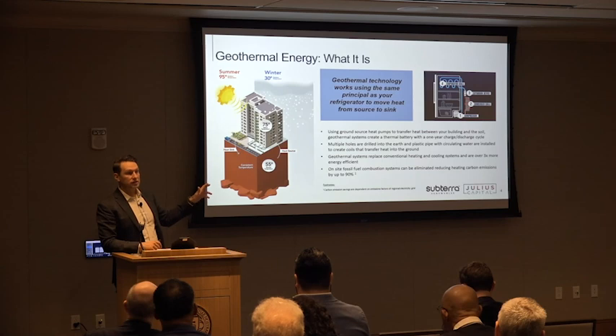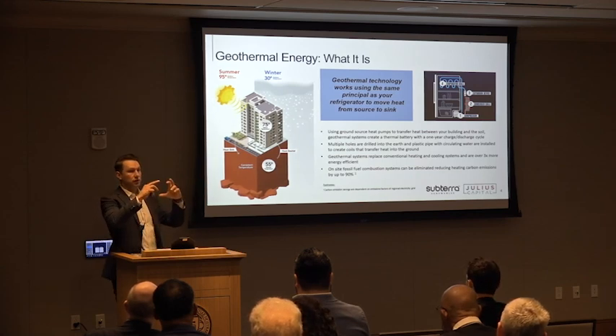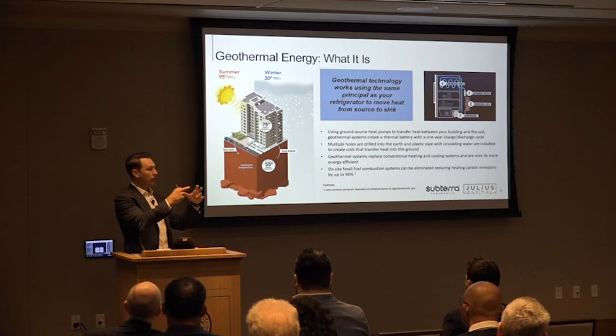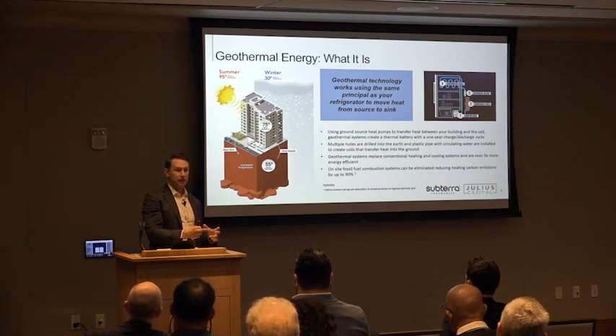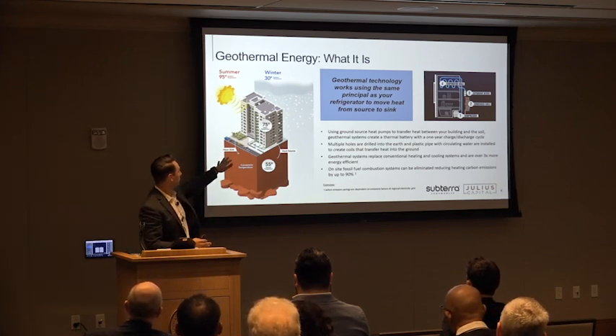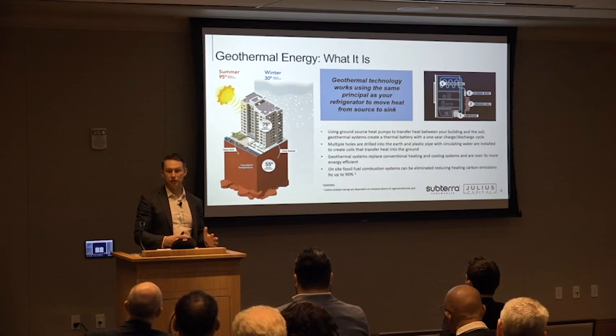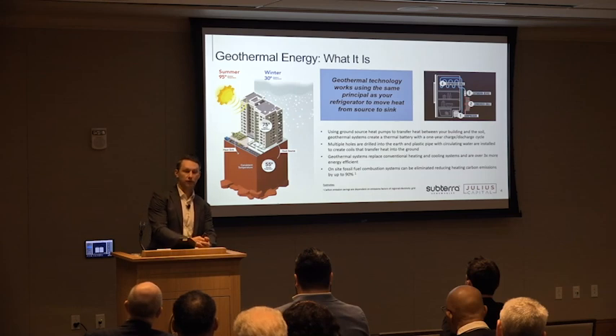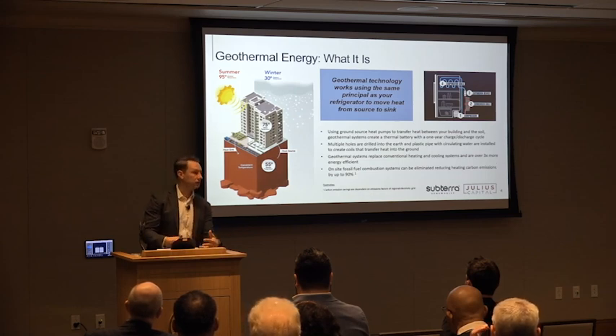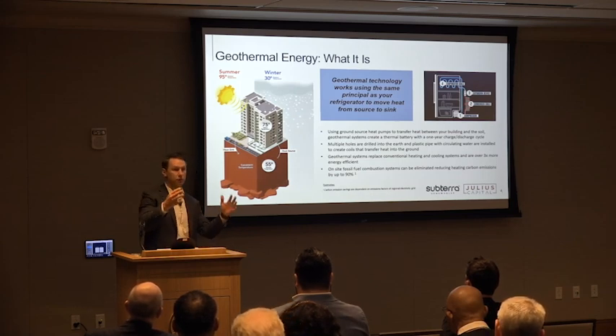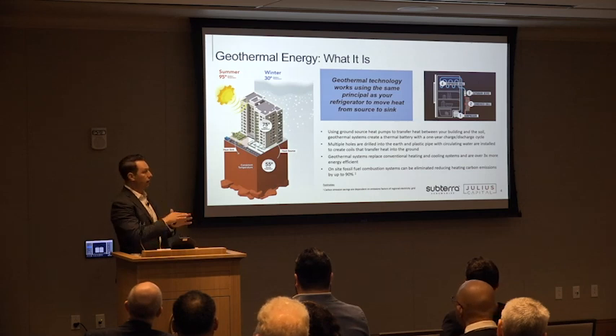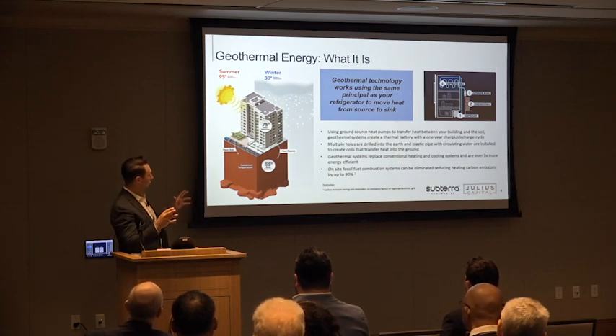What this looks like in your building is a number of boreholes, picture a 6-inch diameter borehole going down about 1,000 feet. For a typical point tower like this, you might expect 50 to 100 boreholes. For a campus like this, or other projects we're doing, you might have 1,000 to 2,000 boreholes. All of these are drilled into the ground, connected with piping, and we circulate fluid through them, creating your coil.